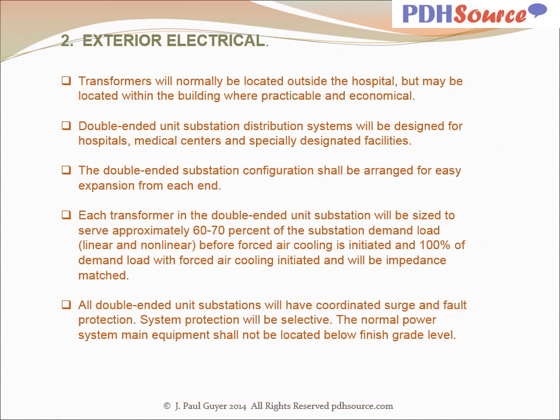Transformers will normally be located outside the hospital, but may be located within the building where practicable and economical. Double-ended unit substation distribution systems will be designed for hospitals, medical centers, and specially designed and designated facilities. The double-ended substation configuration shall be arranged for easy expansion from either end. Each transformer in the double-ended unit substation will be sized to serve approximately 60 to 70% of the substation demand load, linear and nonlinear, before forced air cooling is initiated, and 100% of demand load with forced air cooling initiated, and will be impedance matched.